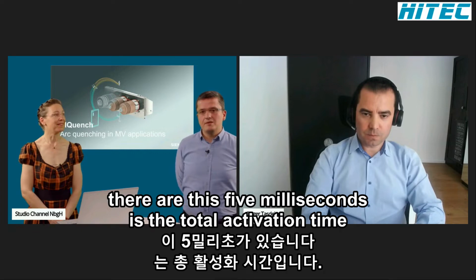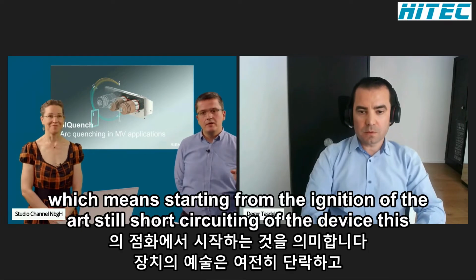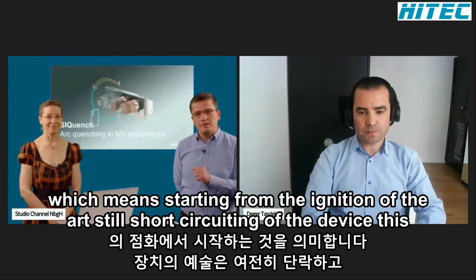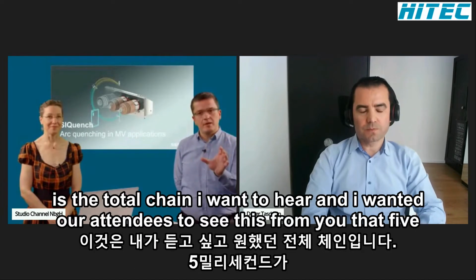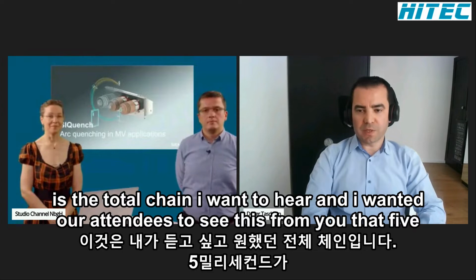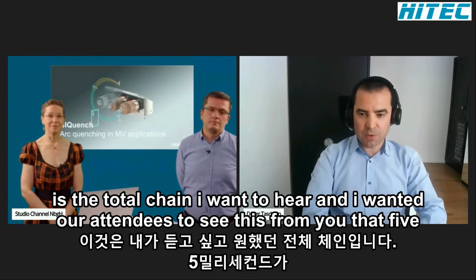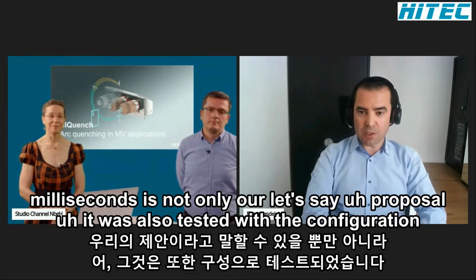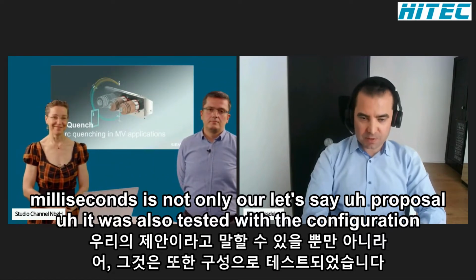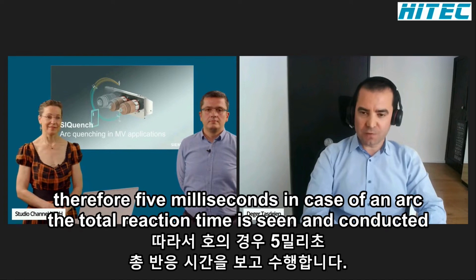This 5 milliseconds is the total activation time, meaning starting from the ignition of the arc till short circuiting of the device. This is the total chain timing. I want our attendees to hear from you that 5 milliseconds is not only our proposal, it was also tested with the configuration. Therefore, in case of an arc, the total reaction time of 5 milliseconds is seen and conducted.